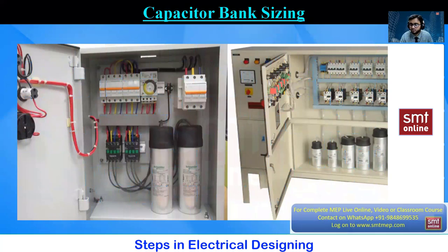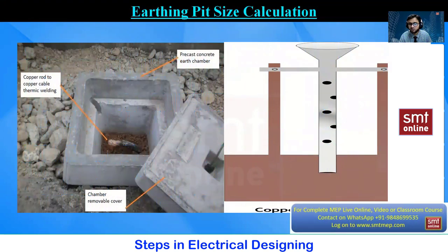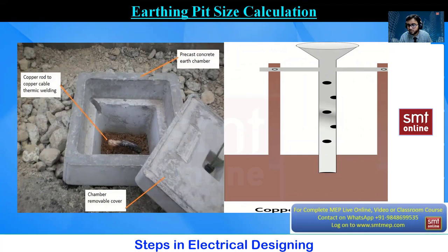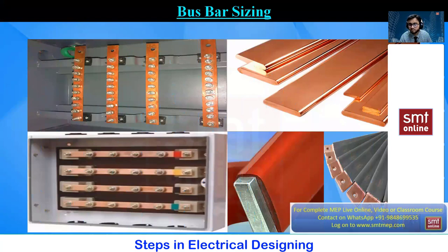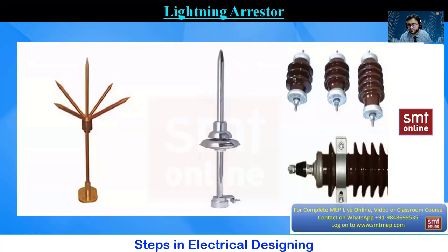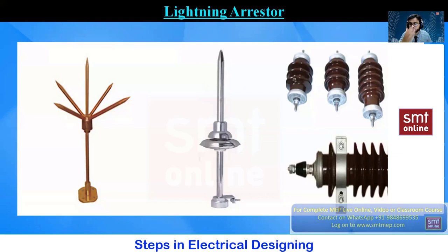A capacitor bank is used to enhance and maintain the power factor. For earthing, we work with the traditional concept to find the earth resistance value and the number of earthing pits — different countries have different standards, and satisfying the earthing range is essential for project approval. For bus bar sizing, copper, aluminium, or galvanized iron conductors with insulation are used. For lightning arresters, high-rise buildings, petrol stations, or projects with solar panels, boilers, or chillers on the roof require lightning protection, as these may attract lightning especially in rainy conditions.